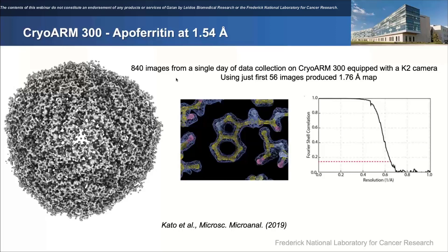The easiest solution was to simply avoid the problem by leaving the objective lens setting constant throughout the data collection session and using the stage to achieve the desired defocus. We knew there were potential practical problems — achieving the desired defocus by moving the stage and possible drift from moving the stage more than normal — so we weren't sure how it would perform. But we wanted to give it a shot. Luckily, we had a JEOL Applications Engineer named Taku Fukumura stationed in the lab, and he was confident he could script everything in and that it would work properly without huge effects on data quality or throughput.